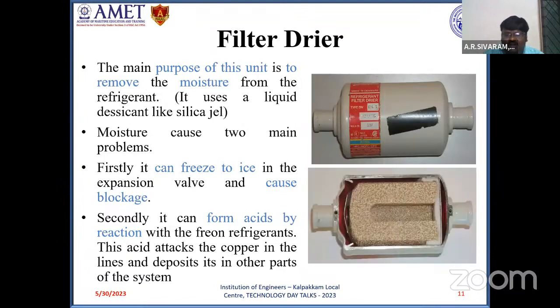And usually a filter dryer will be present before the expansion valve, in between the receiver and the expansion valve. The main function of this component is to filter out the moisture content present in the refrigerant. Generally, it will have a desiccant inside it. Desiccants are substances which can hold 27 to 28% of their weight in moisture or water vapor content. Normally in domestic and commercial systems, silica gel is used as a desiccant. The silica gel inside this filter dryer absorbs the moisture present in the refrigerant, and the moisture free refrigerant leads to the expansion valve.